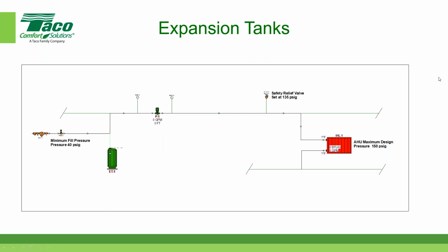So therefore, the pressure that we want in the piping system before we get to the relief valve, let's say I stick a pressure gauge here, we want that to be about 5 pounds below the relief valve setting. So I want that pressure to be about 130 pounds. So I'm going to put that in there next, 130 pounds. There it is, 130 pounds, and that's the pressure also I want at the discharge side of my pump.